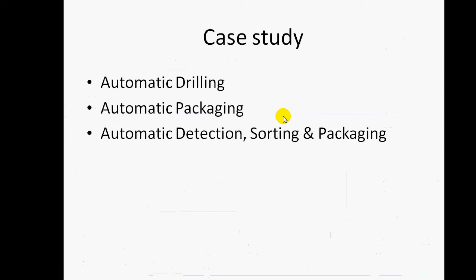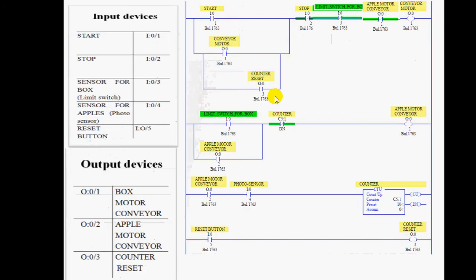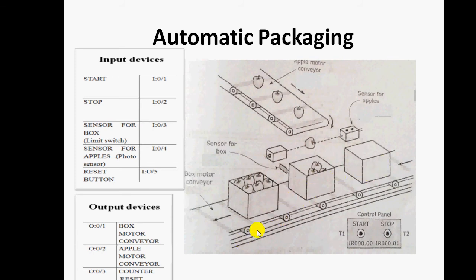Now we discuss automatic packaging. Two conveyors are provided: the first conveyor is for moving the boxes and the second conveyor is for moving apples. When you press the start button, the box conveyor starts. When the box contacts the sensor, the box conveyor stops. After that, the apple motor conveyor starts, and whenever a count of 10 apples is reached, the box conveyor starts again and moves the box to the next position.